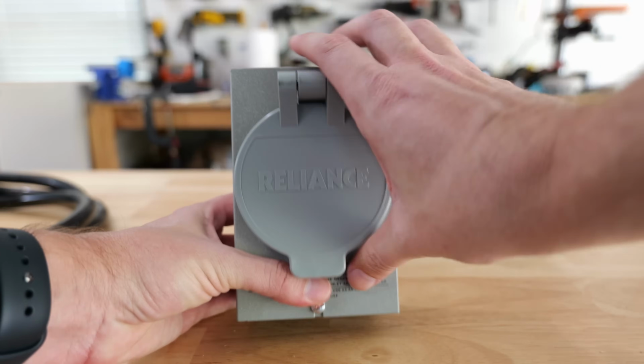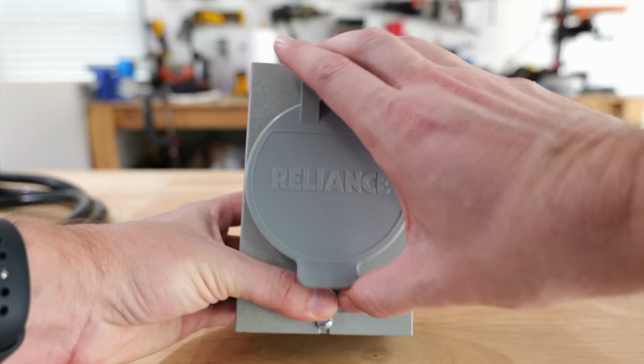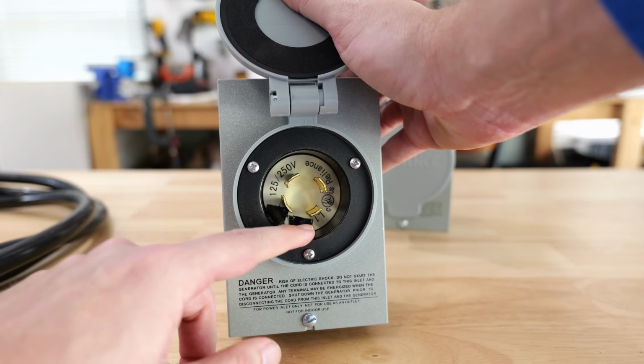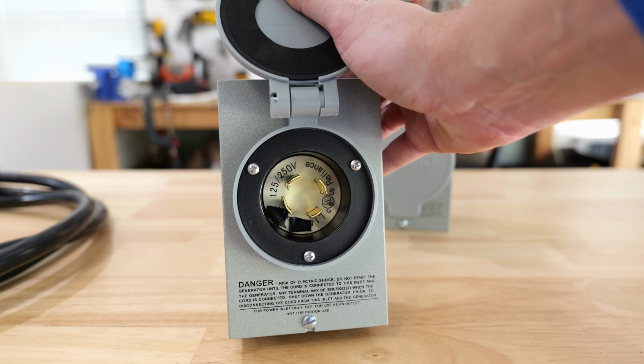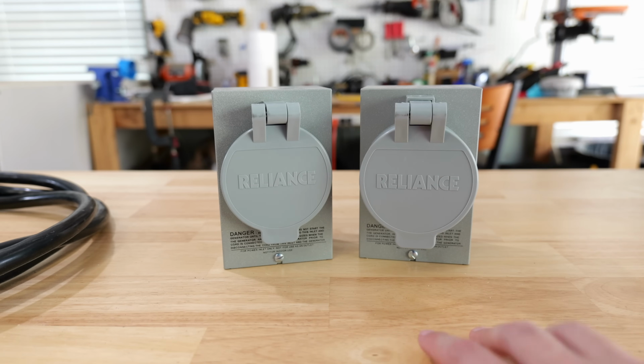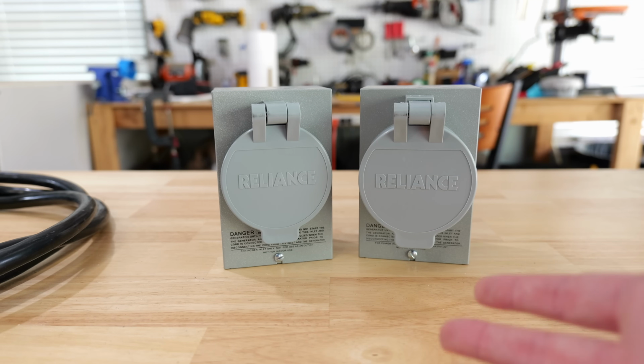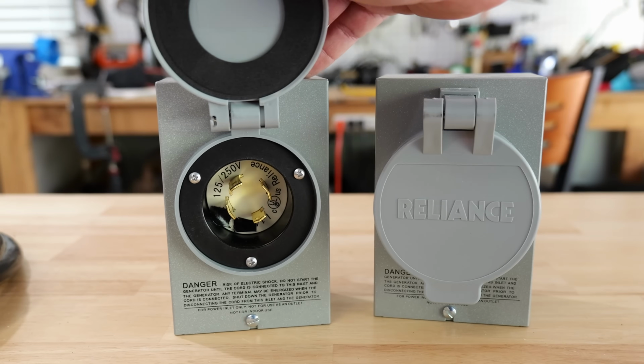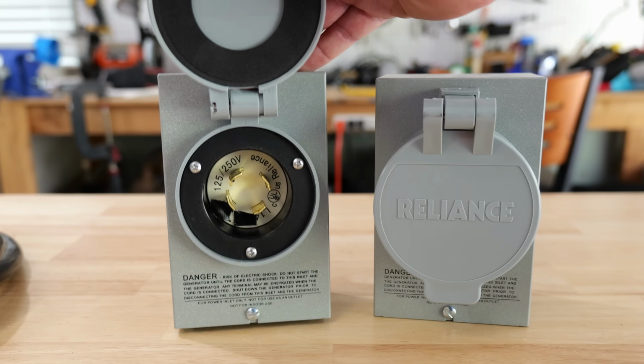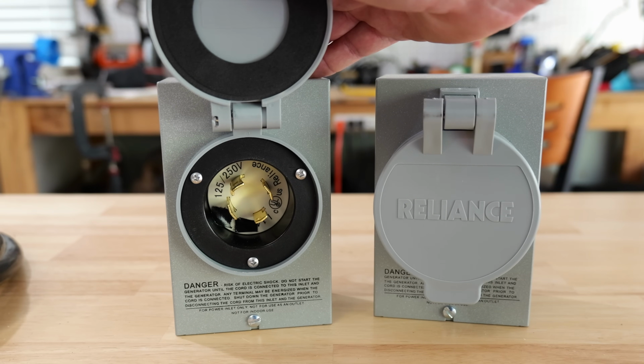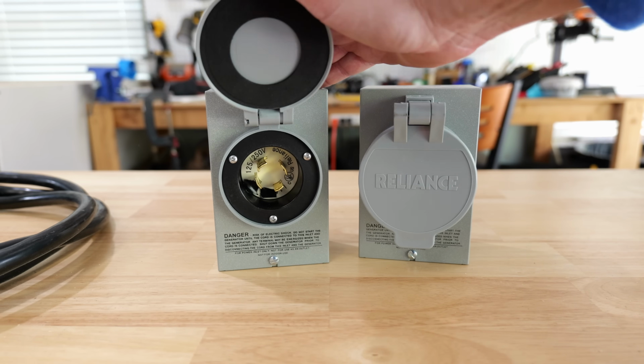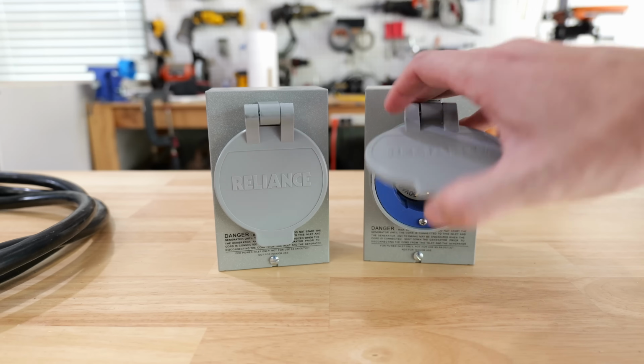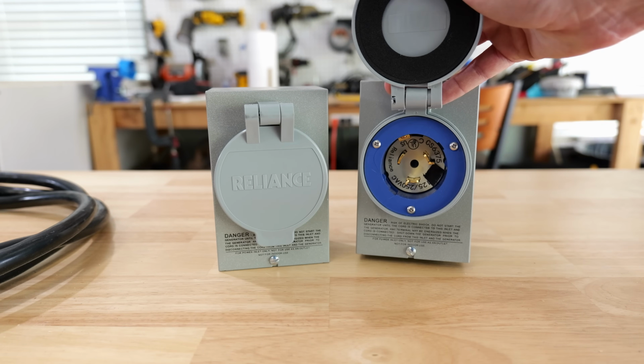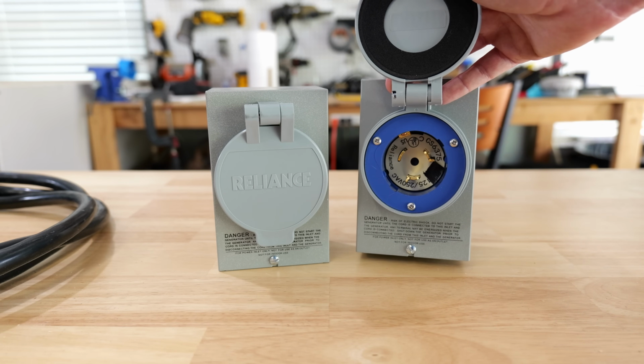And then this one over here, again, they're both the same dimensions. If we open it up, this one has four prongs. So they each have a different number of prongs. This one has three, this one has four. So which one is the 30 amp and which one is the 50 amp? I would venture to guess that most people would guess that this one with the four prongs is the 50 amp power inlet box, and you would actually be incorrect. The one with the three prongs is actually the 50 amp power inlet box.